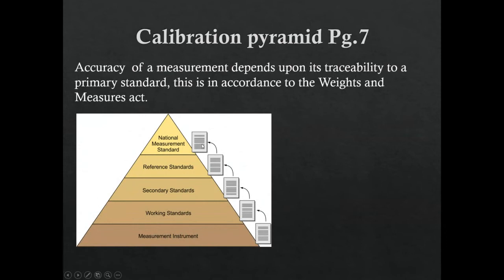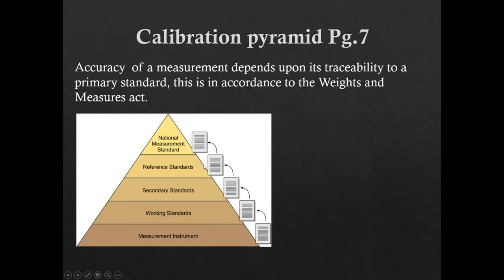Documentation goes along with all of this. The accuracy of the measurement depends upon traceability to a primary standard in accordance with the Weights and Measures Act, overseen by Measurement Canada. Every time a standard gets calibrated or created it comes with a piece of paper — for example, 'this is a kilogram plus or minus 0.00000001 grams.' Each step in the chain comes with paperwork telling us the degree of accuracy we should expect from that standard.